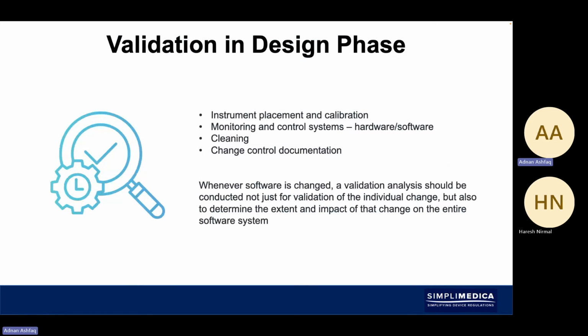So when we are doing validation in design phases, we should look at different aspects. As I've mentioned before, you would look at validation, analysis, verification, but also changes in the design. And this happens quite commonly, especially if you've got a very complex piece of equipment, which is taking a lot of time and you have to work closely with the suppliers.